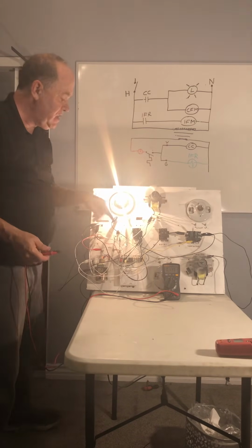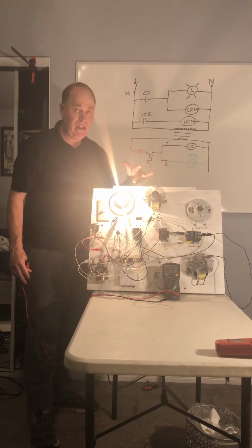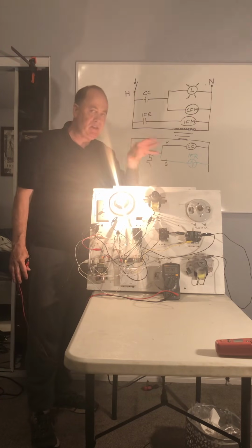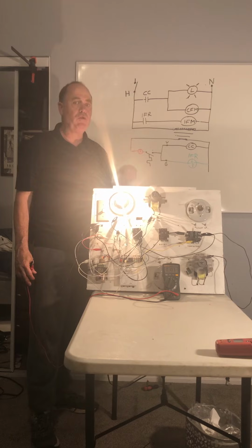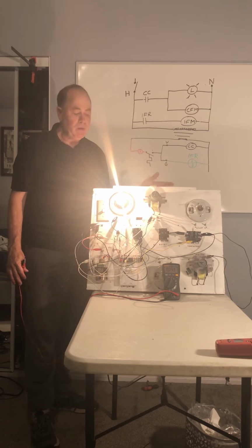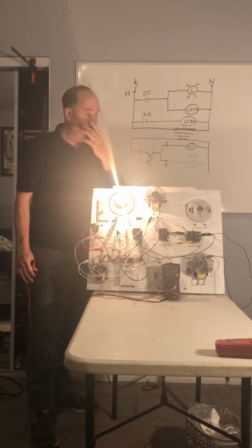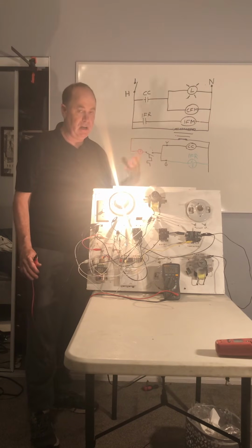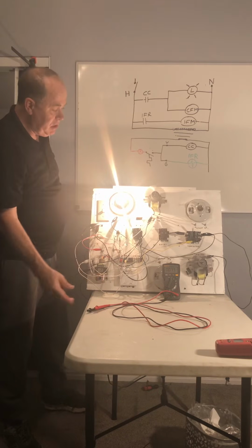So that is being pulled in, and the same thing is happening here with the coil on the indoor fan relay. And relays and contactors can be 24 volt coil, 120 volt coil, 230 volt coil, what have you. And you have to use the right contactor or relay with the right voltage. These are designed to run at 24 volts, and we've wired them up that way. Again, not much amperage is going through.